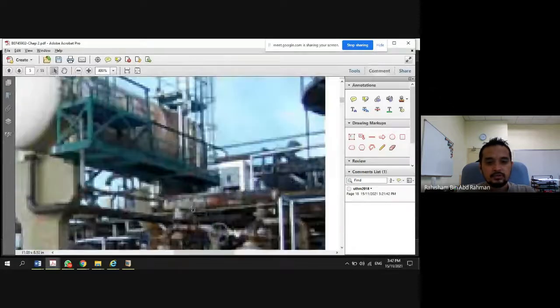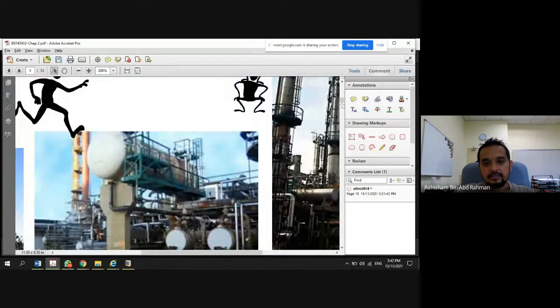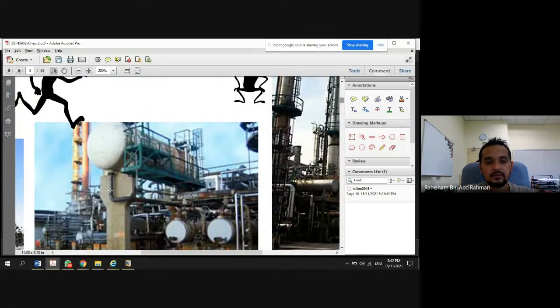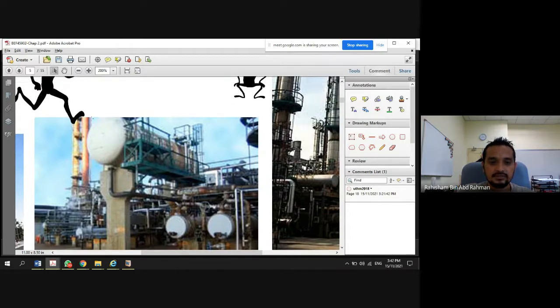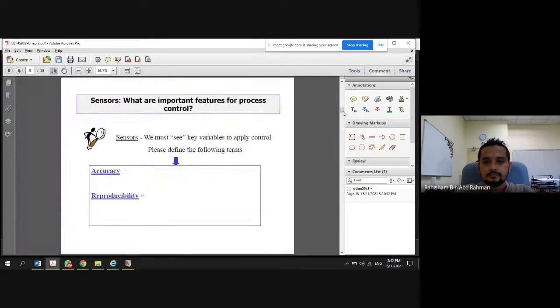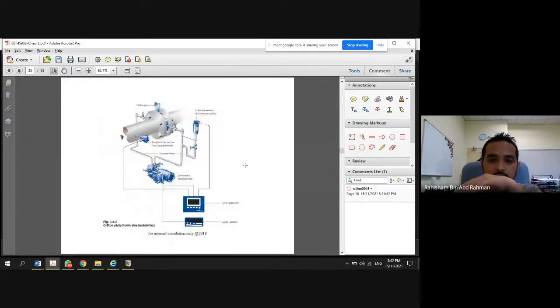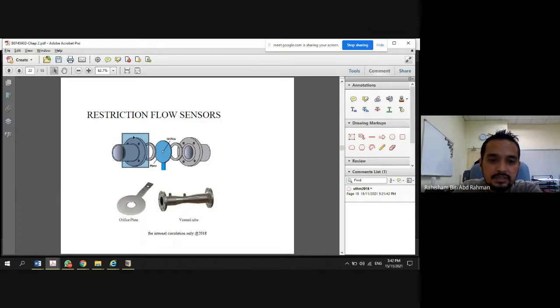Okay, if we look here as an example, here we find an orifice, here we find an orifice, here there is an orifice plate, a pressure sensor, a flow sensor, because they are very, very important. This is the vessel, and the flow rate is very important for a certain process, a chemical process, a certain production criteria. So that's why in just a few meters of pipeline, they will have flanges where they install the orifice plate. So we will continuously see this kind of arrangement.